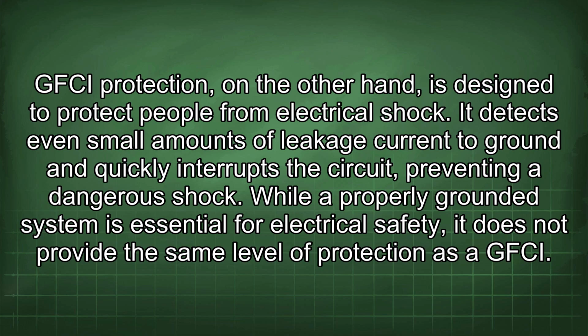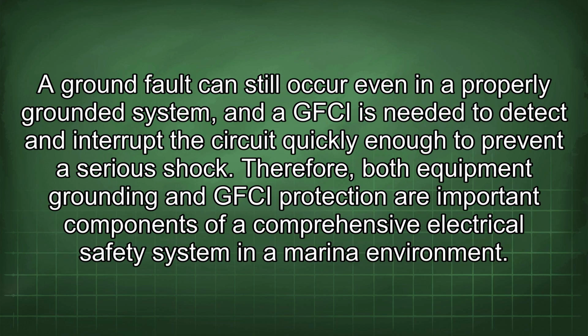While a properly grounded system is essential for electrical safety, it does not provide the same level of protection as a GFCI. A ground fault can still occur even in a properly grounded system, and a GFCI is needed to detect and interrupt the circuit quickly enough to prevent a serious shock. Therefore, both equipment grounding and GFCI protection are important components of a comprehensive electrical safety system in a marina environment.